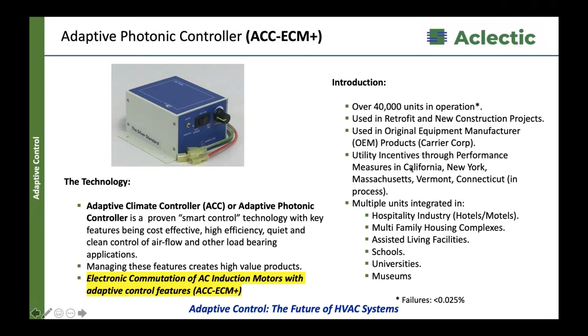How does it do that? In that little 4x5 box, it's like a microprocessor, but for power. It takes in fixed electricity, and you can program various inputs and outputs to adapt and make that electricity smart. What enables it to do that is reading real-time conditions: temperature, humidity, oxygen, CO2, building management system, voltage input 0 to 10 - that unit will take any of those signals. Based on what those signals are doing, it takes the program and adapts the output power, converting fixed incoming power into smart adaptive output power to control the units in that system.